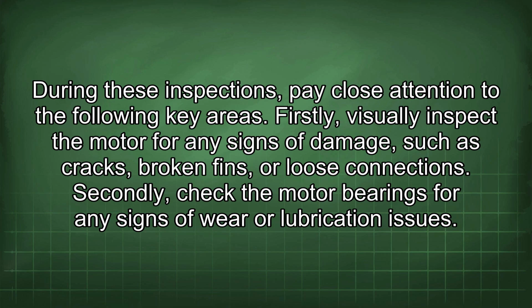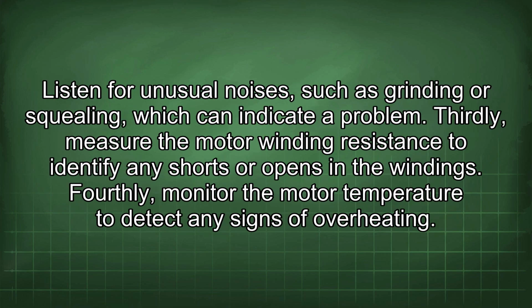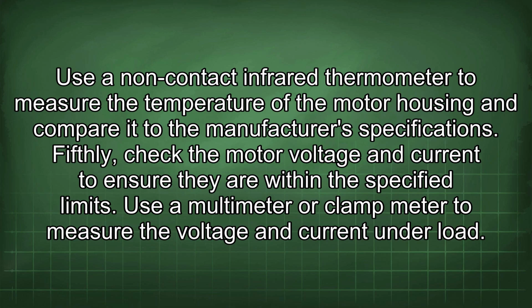Secondly, check the motor bearings for any signs of wear or lubrication issues. Listen for unusual noises, such as grinding or squealing, which can indicate a problem. Thirdly, measure the motor winding resistance to identify any shorts or opens in the windings. Fourthly, monitor the motor temperature to detect any signs of overheating. Use a non-contact infrared thermometer to measure the temperature of the motor housing and compare it to the manufacturer's specifications.